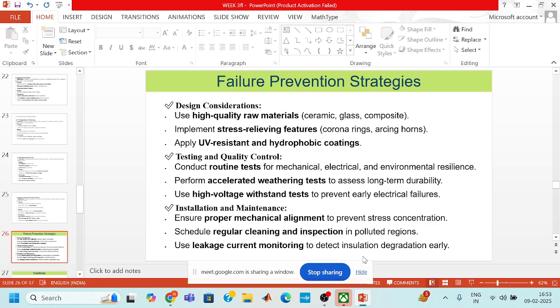There are some prevention strategies, like design considerations. We have to use high quality raw materials for ceramic, glass, and composite, implement stress relieving features like corona rings and arcing horns, and apply UV resistant and hydrophobic coatings. Second is testing and quality control. We have to conduct routine tests for mechanical, electrical, and environmental resilience, and perform accelerated weathering tests to assess long-term durability. We can also use high voltage withstand tests to prevent early electrical failures.